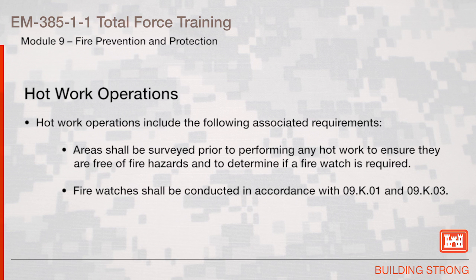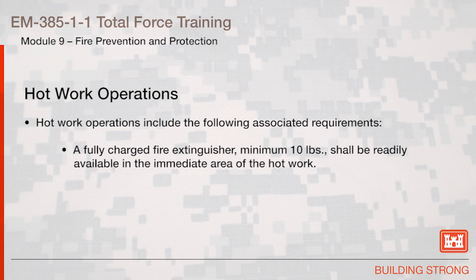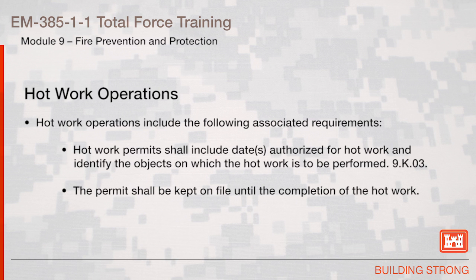Hot work operations include the following associated requirements. Areas shall be surveyed prior to performing any hot work to ensure they are free of fire hazards and to determine if a fire watch is required. Fire watches shall be conducted in accordance with sections 09.K.01 and 09.K.03. A fully charged fire extinguisher, minimum 10 pounds, shall be readily available in the immediate area of the hot work. Hot work permits shall include dates authorized for hot work and identify the objects on which the hot work is to be performed. The permit shall be kept on file until the completion of the hot work.